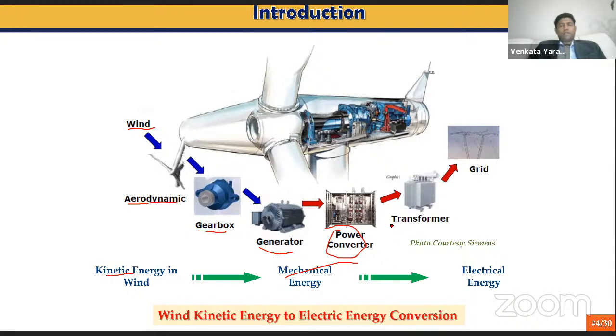The output of the power converter is usually less than 4,000 volts. But in order to connect to the grid and transfer power at maximum efficiency and lower losses, we need to step up the voltage. So we use a transformer to step up the voltage, usually from 690 volts to 33 kV, connected to the wind farm collection point. Then we have another transformer to connect to the main grid of the transmission system.